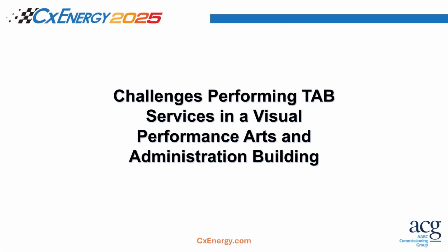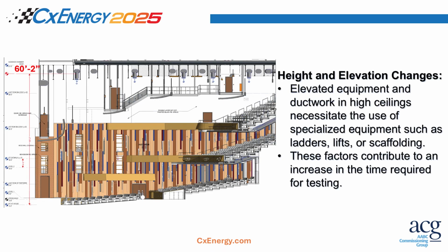And then we'll go into some of the challenges that we faced when we balanced that performance arts building. So obviously, height and elevation changes are always going to be involved with performing arts. Elevations of the equipment, ductwork, and high ceilings made it very difficult to balance.